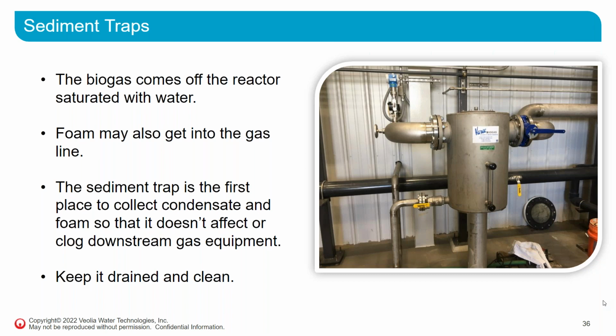And if you have that moisture or those clogs in the line, it affects your ability to control the pressure in the reactor, which is not good for either safety or performance. And it's important to keep sediment traps drained and clean.